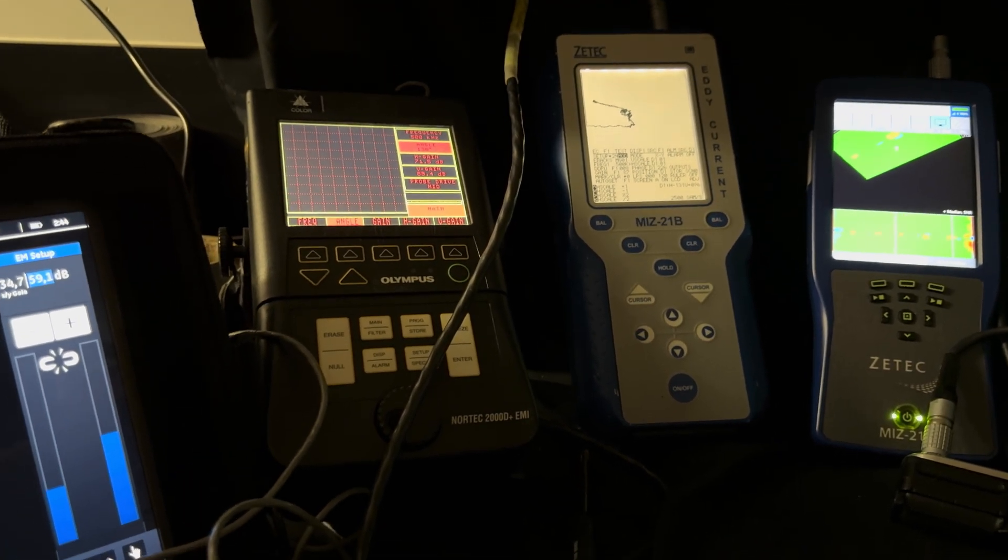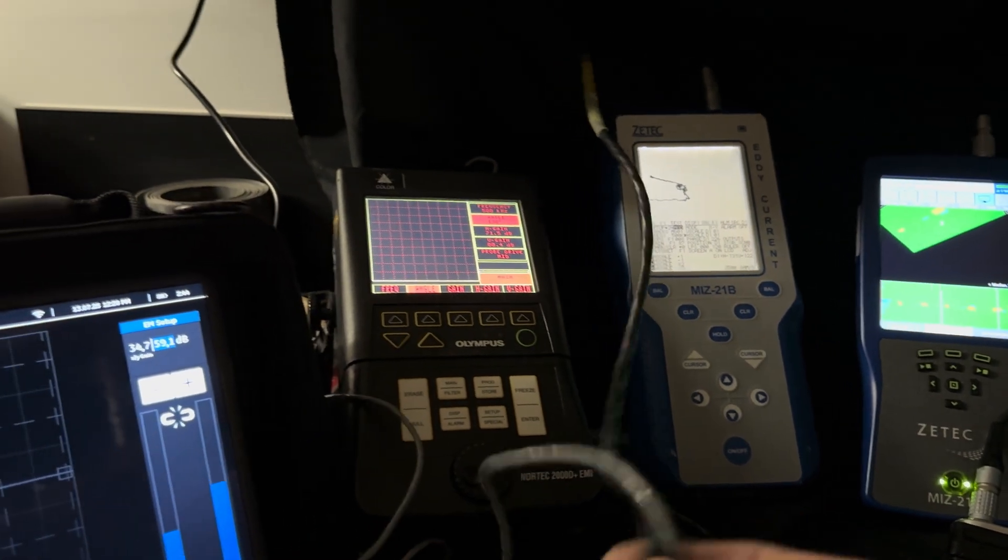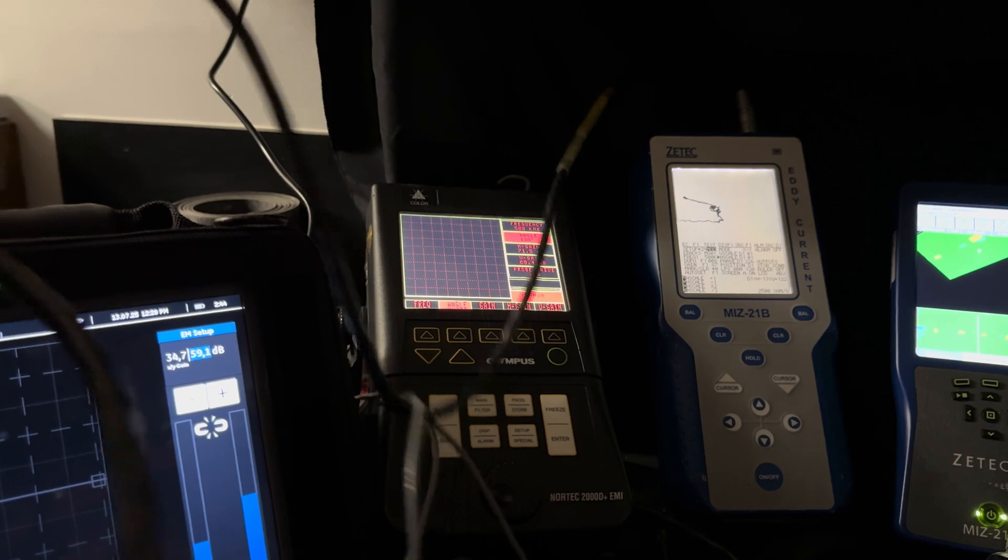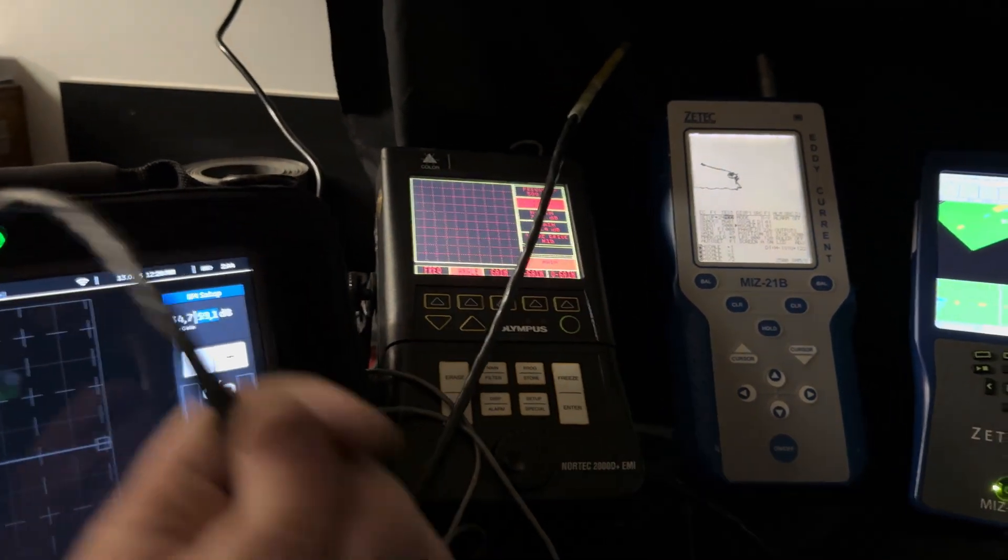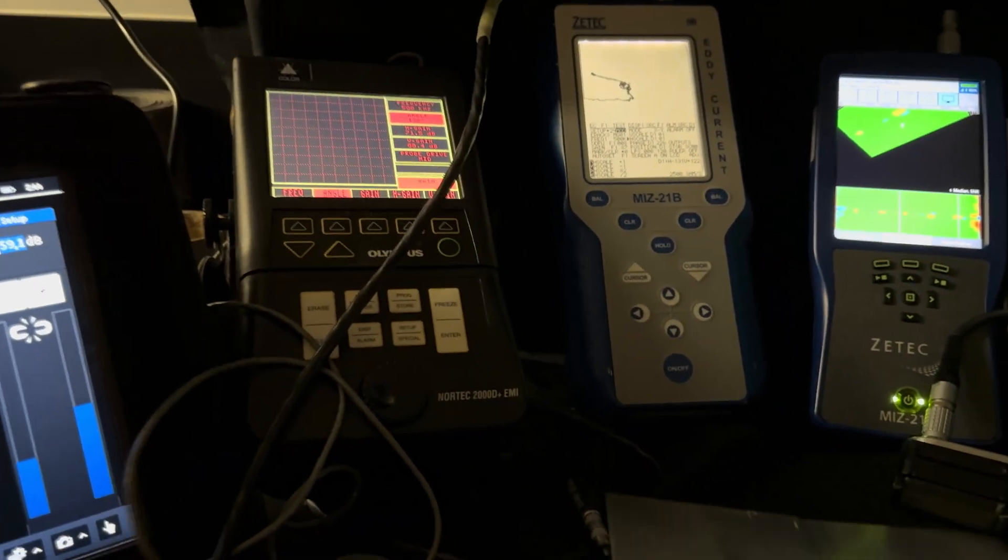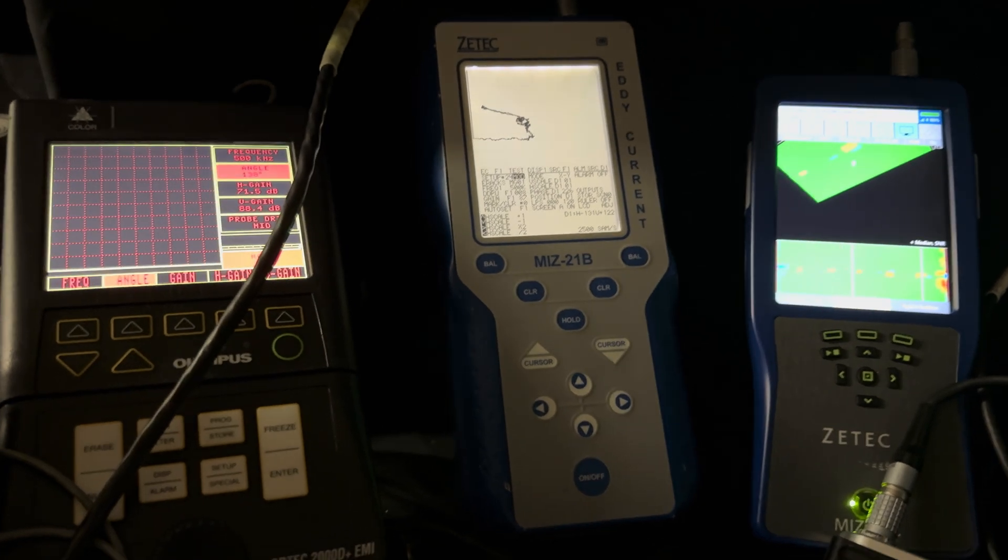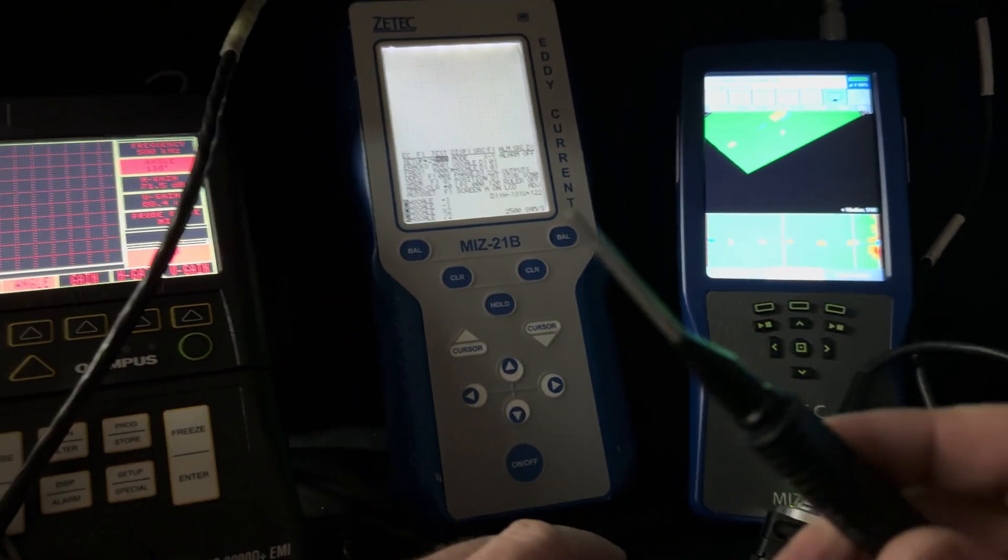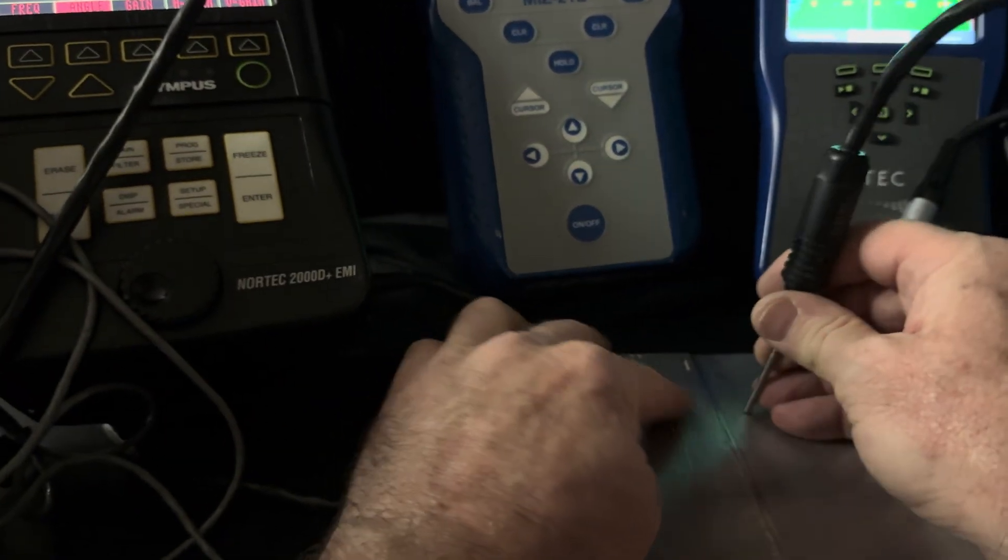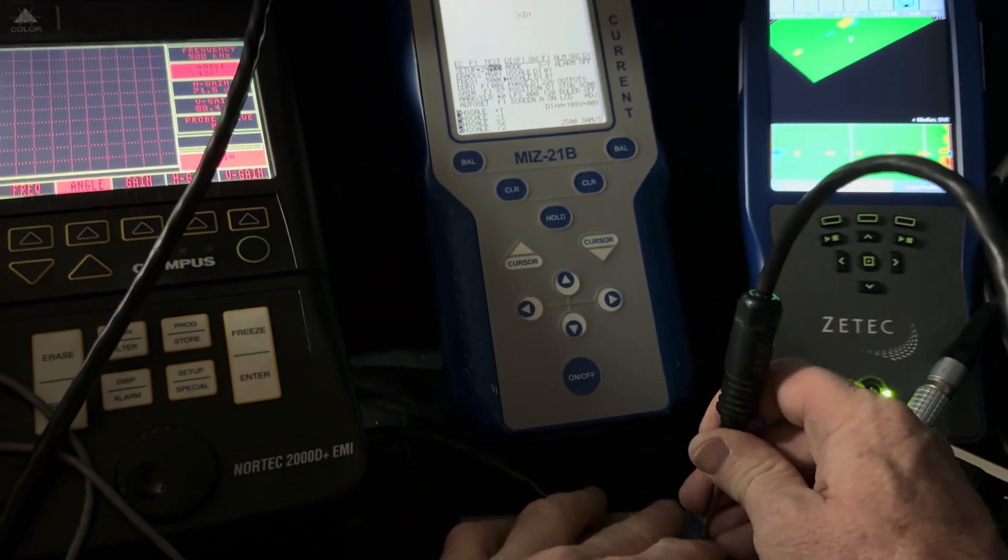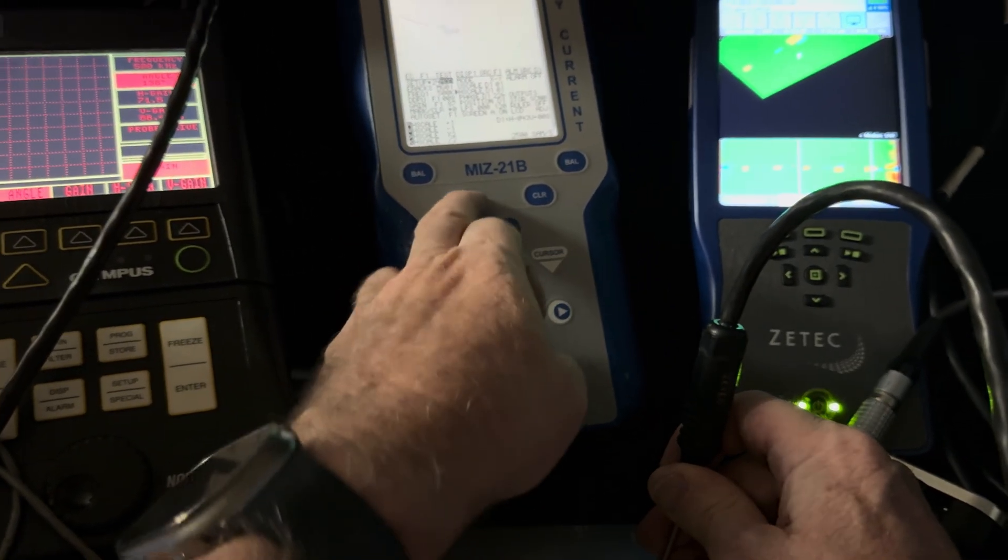So you're never going to get the exact same results from one tester to the next on the same frequency. So that's why you have to do a specific calibration each time you do a test. You got to set it up as best as you can with the tester, cable, and probe that you have. We're just going to go through some of these instruments. I'm going to start with the MIZ-21B first because I've had it on for a long time and it's not plugged in so the battery is not gonna last much longer.